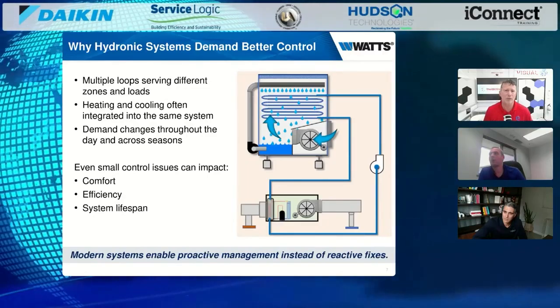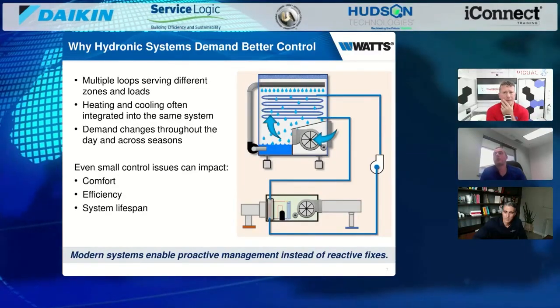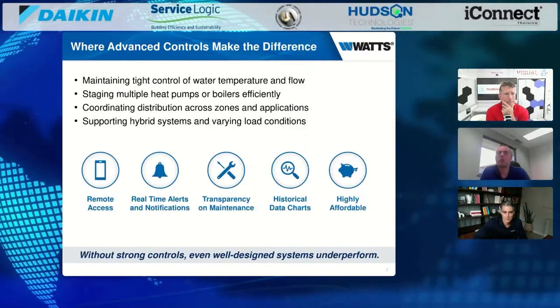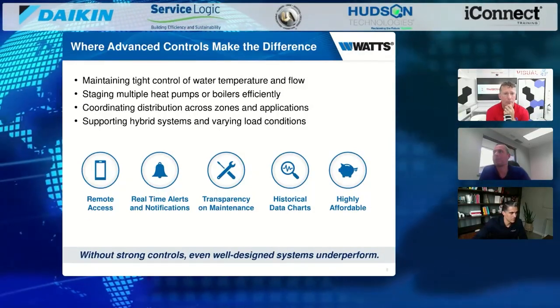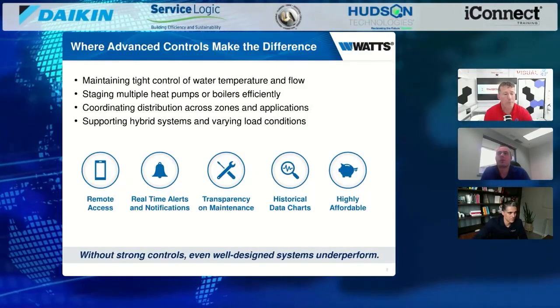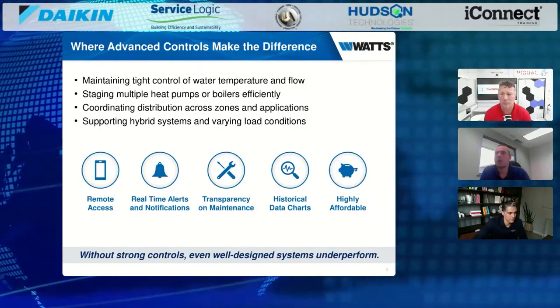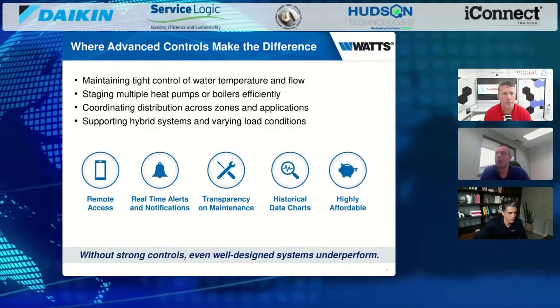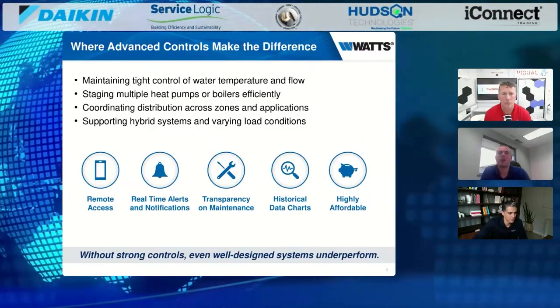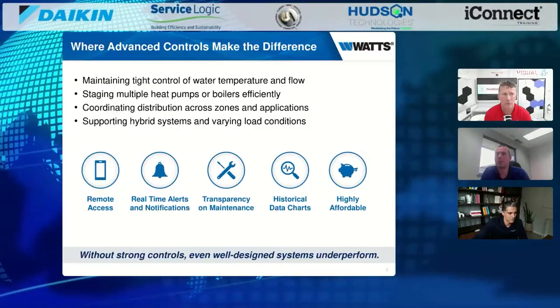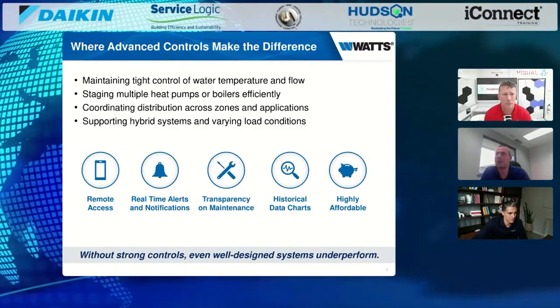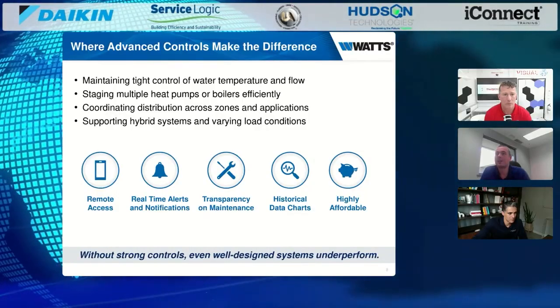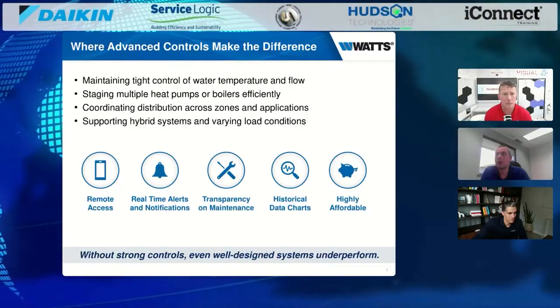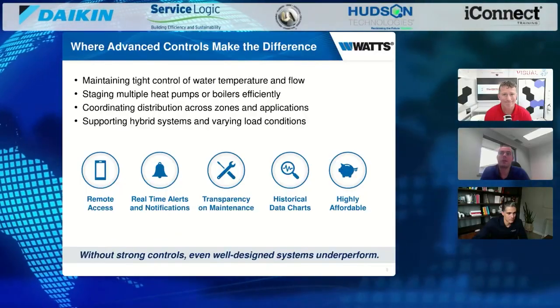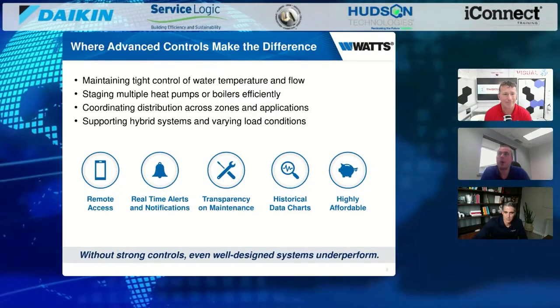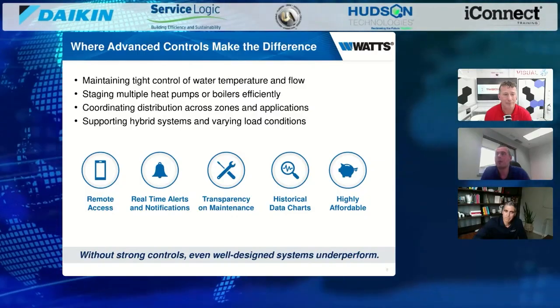So, scalable too. We talk about what's the advantage of this type of advanced control solution. Maintaining the water temperature, pressures, and flow, that's key. That's going to operate all your equipment and maintain and save lifetime on your equipment. Staging the equipment, so when does the second stage come on, when do we need the third source, and really optimizing that for energy use.